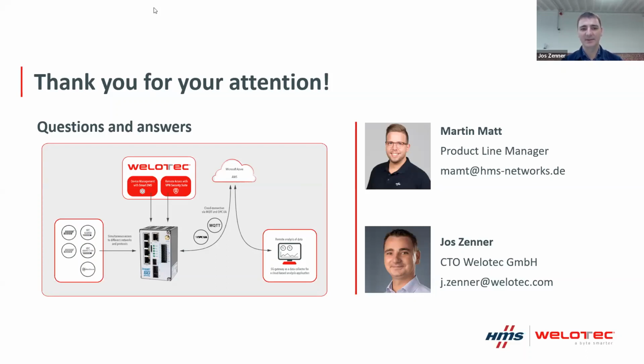At decentralized locations we use S7 from Siemens. Can we use any S7 with Profibus and Profinet? Yes, you can. Our device is just a Siemens device in that case. You can freely configure the GSD file in the SG Gateway, download it, and feed it into the S7 system from Siemens. That's basically it, so that's definitely a yes.